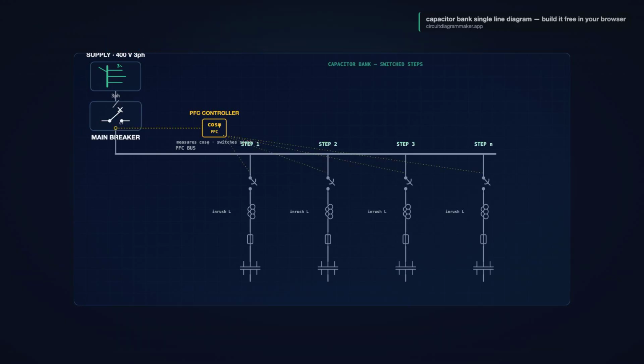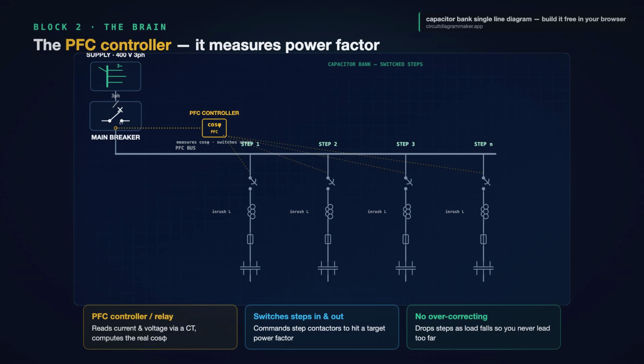Block 2 and the brain of the whole thing, the power factor correction controller. The controller sits off to the side and watches the incoming line, usually through a current transformer, a CT, clamped on the feeder. From the current and the voltage, it computes the real power factor, the cosine phi, right now. Then it does the one job the whole bank exists for. It switches capacitor steps in and out to hit a target power factor, typically around 0.95. If the plant draws more reactive power, it brings more steps in. If the load falls, it drops steps out so you never overcorrect and swing the other way. The controller is what makes this an automatic bank, not a fixed one.